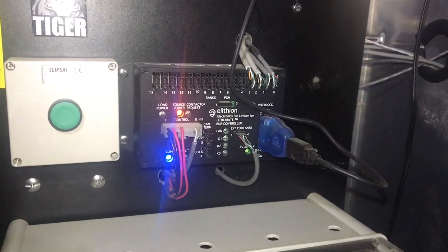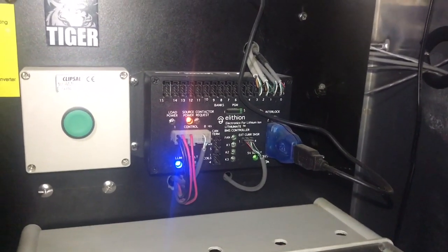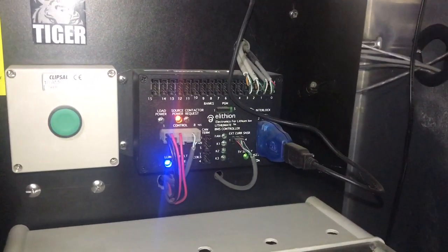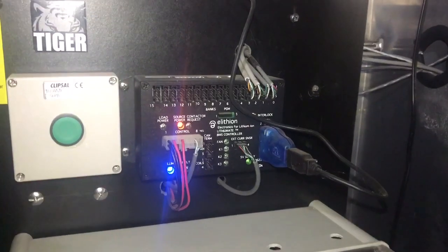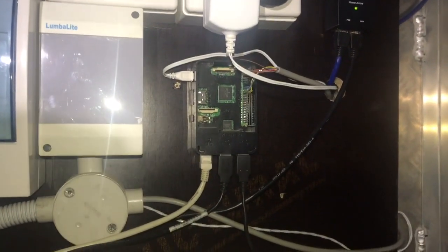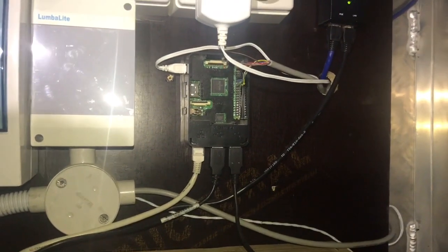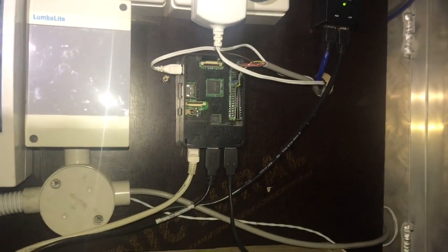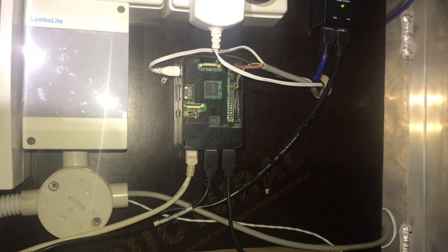So it does all that logic and says you should limit charge to 80%, 90%, 10%, etc. of maximum charge rate. I can read that in and if it's asking me to limit the charging as it gets full and starts balancing to, say, 50% of maximum charge rate, I then use the Selectronic charge profiling to manually trigger that.